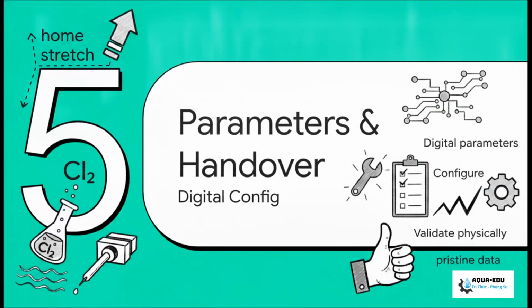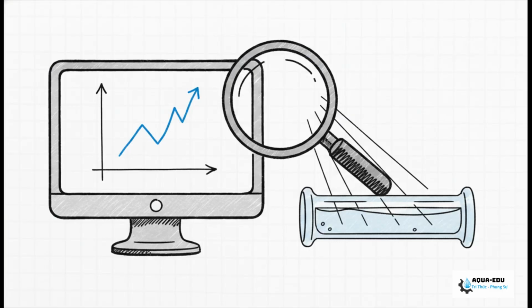We're getting close now. Section 5, parameters and final handover. Over on the panel PC, set your measurement range from 0.025 to 1.5 milligrams per liter. Configure a 5-minute measurement interval. This is really the sweet spot for tracking source water fluctuations. Input your high alarm at 0.5 and your low at 0.05.